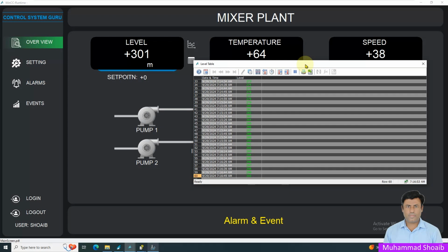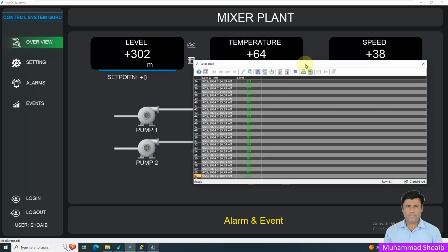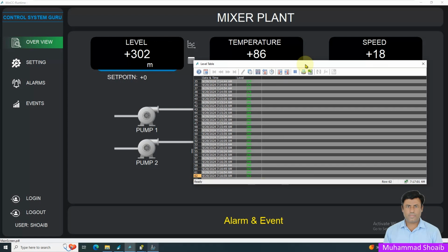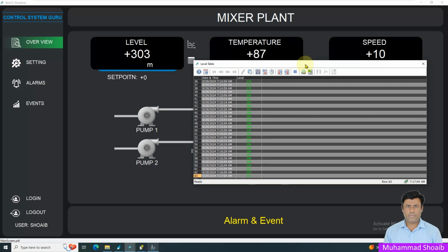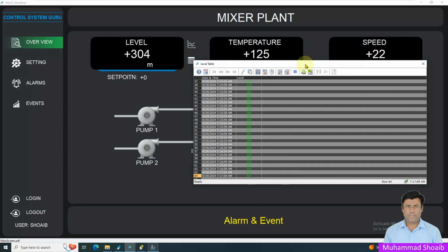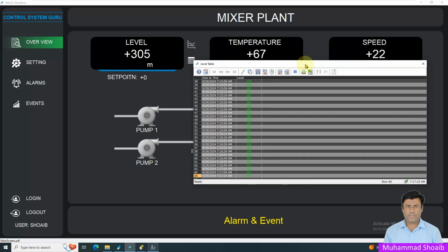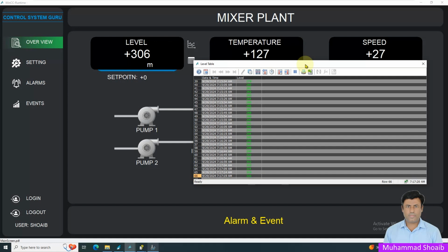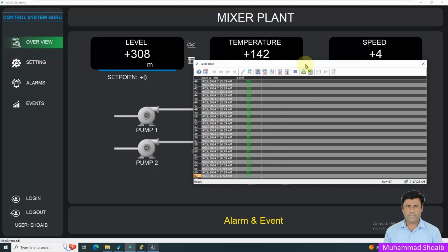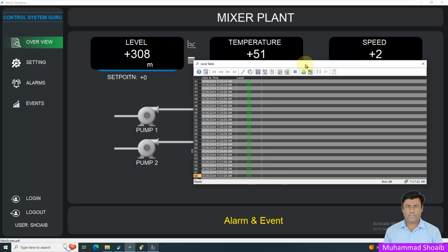or when a specific boolean value is triggered, or a specific button is pressed in the HMI. At that time you want to historize the data. It will not historize continuously as in the previous tutorial, where data was continuously logging. Then we saw that once one bit is true, data is logged. But here it's different. Once the value becomes 0 to 1, it will log data only at that time.